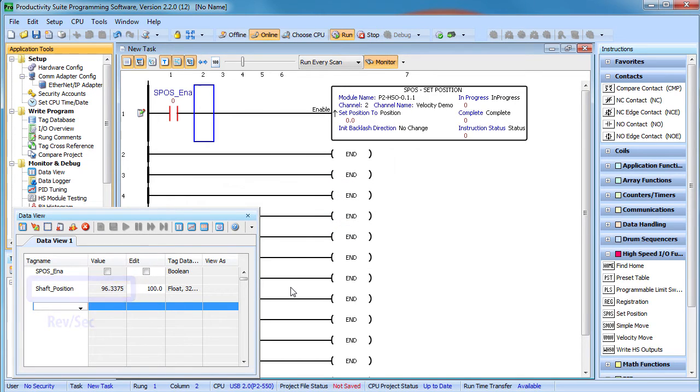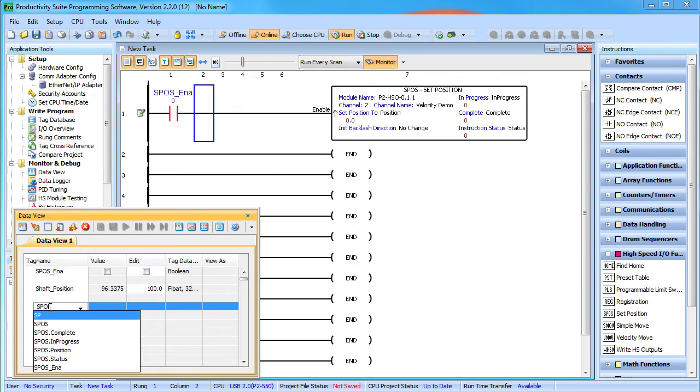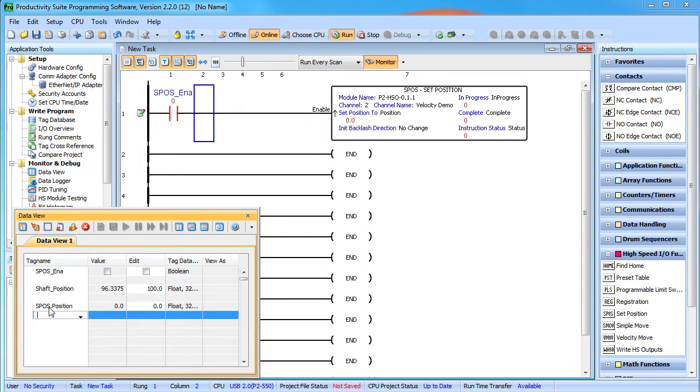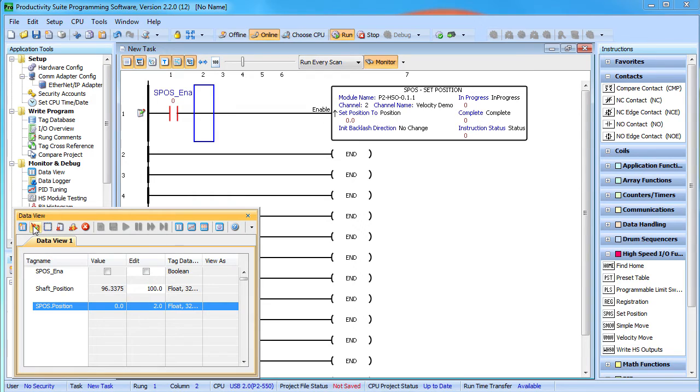The key point here is every pulse that exits the HSO module, regardless of who generated it, is accounted for in this position tag. So let's add the set position structure we created to the data view and change the position to 2. Two what? Two revolutions. Remember, once you set up the units in the hardware configuration, everything in the entire project works in those units.